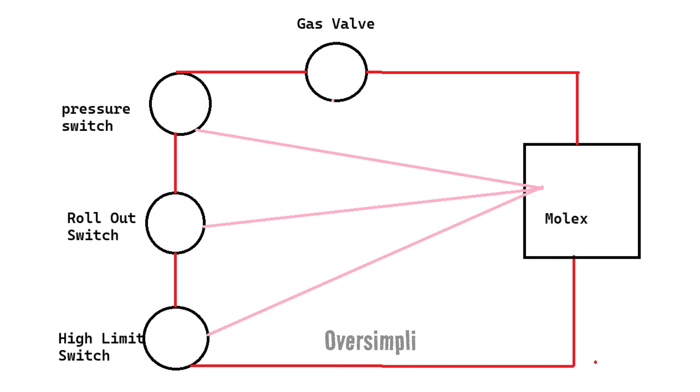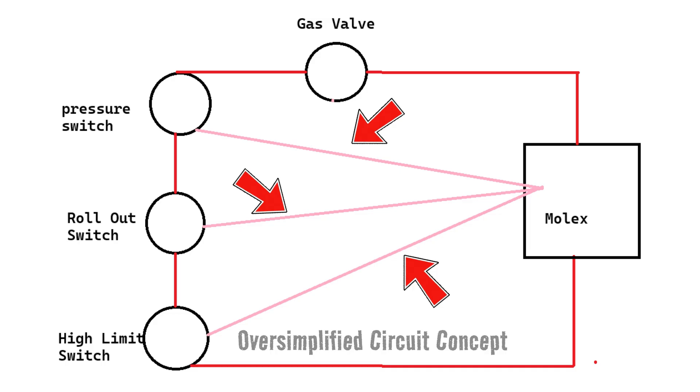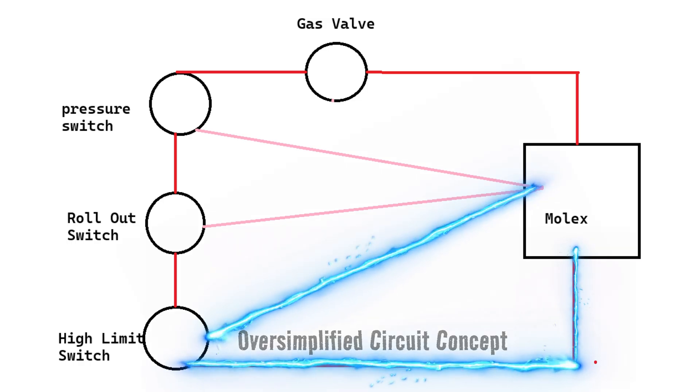What a control board is actually doing with these Molex connections is that each wire coming back from each one of the components is a little nodule. It's a tap point that the control board can read the voltage in different parts of that series circuit. So if 24 volts leaves the Molex plug, it makes it to the high limit switch, goes back to the Molex, and the Molex can confirm, we have 24 volts that far into the circuit.